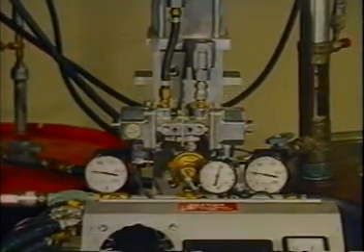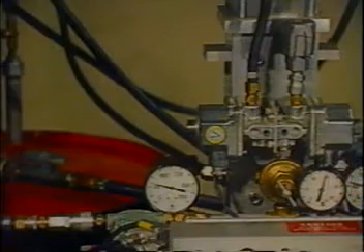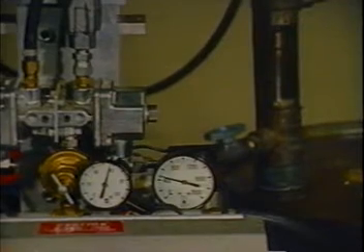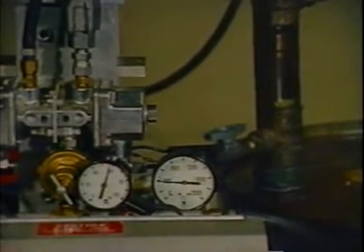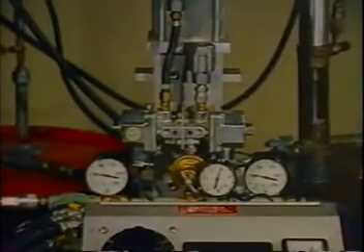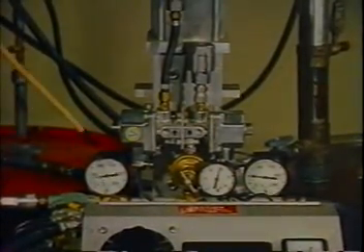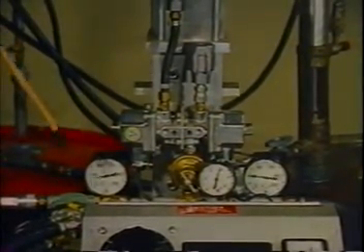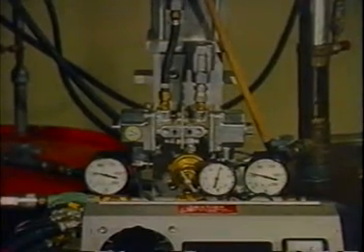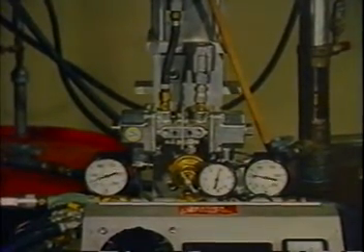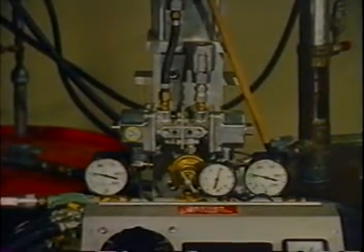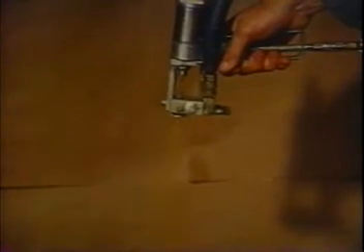In slow motion, notice that during the no-pump portion of the stroke in the cavitating pump, the second pump in the common drive system immediately begins pumping after the top reverse, resulting in momentary loss of ratio control and imbalance of material pressures. The pressure loss in the cavitating pump is accompanied by a pressure increase in the opposite pump, since the cavitating pump offers no resistance to the common drive system as the cavity is closed, and the total driving force is applied to the second pump, which therefore tends to double its output pressure, increasing the effects of pressure imbalance.